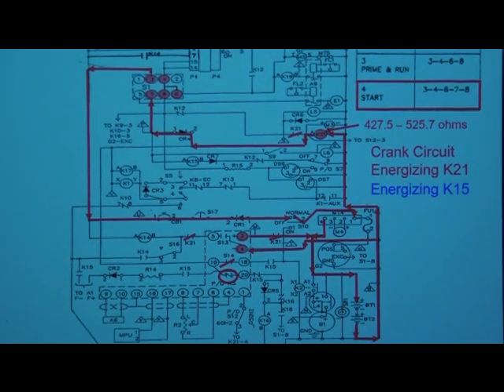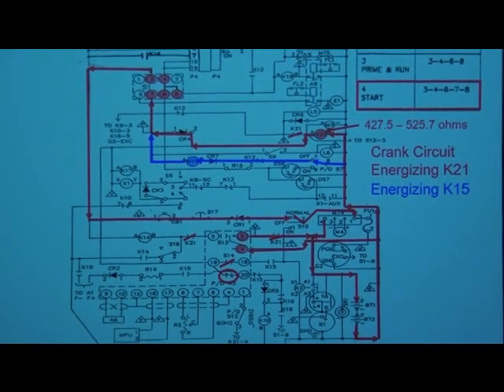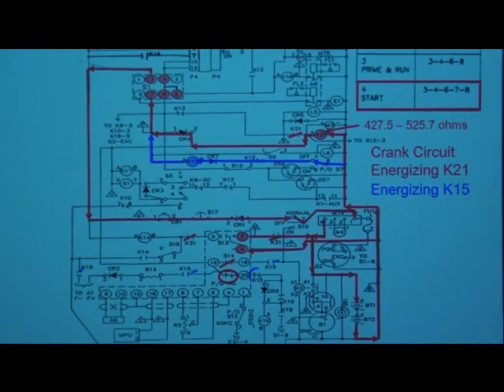Our next step is to energize the K15 start relay. Its contacts are used in order for the K2 crank relay to be energized which allows the L4 starter solenoid and B1 starter motor to engage the flywheel. This path will be illuminated in blue on the wire schematic. We are going to pick up potential from the negative web heading towards our K15 start relay through our CR7 inline diode. We will enter through the K15 pin Bravo and leave out of the K15 pin Alpha. Once we reach this point, we will now follow the common path to the positive side of the battery which was established by the K21 electronic governor control relay. At this point, our K15 start relay is now energized and its contacts have reversed allowing a path for the K2 crank relay.